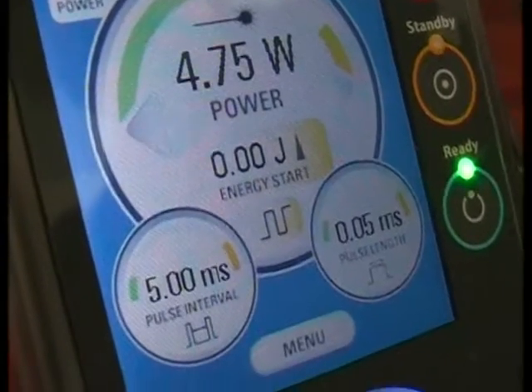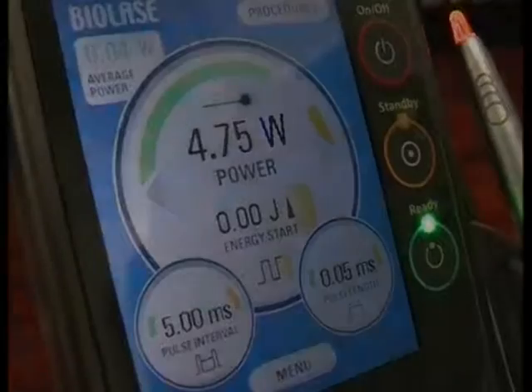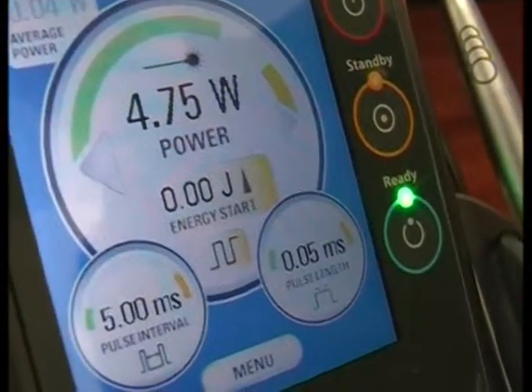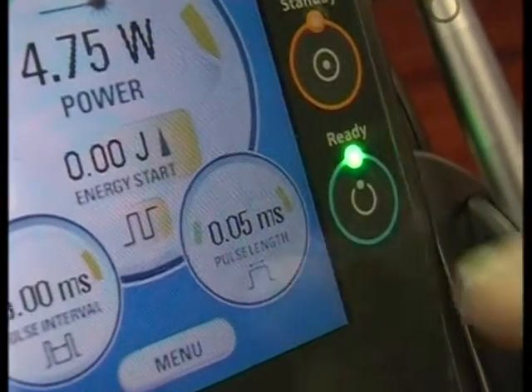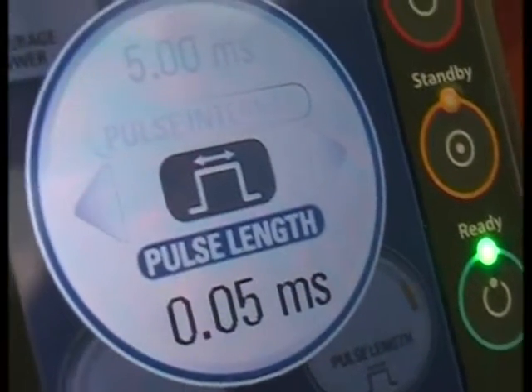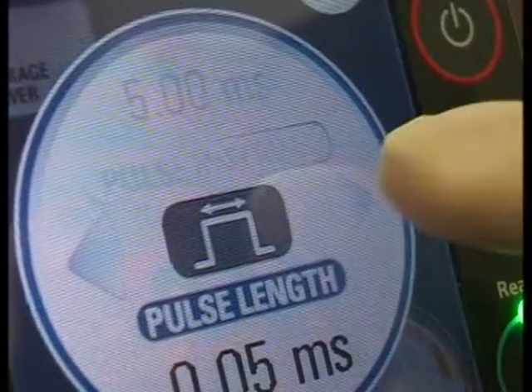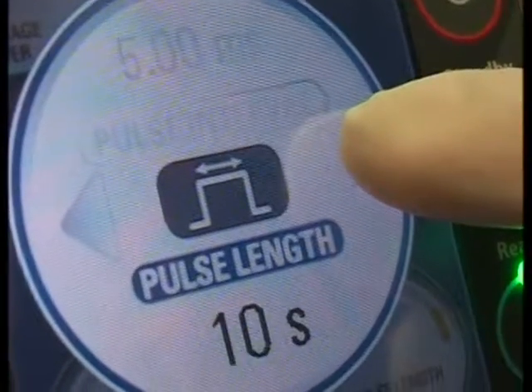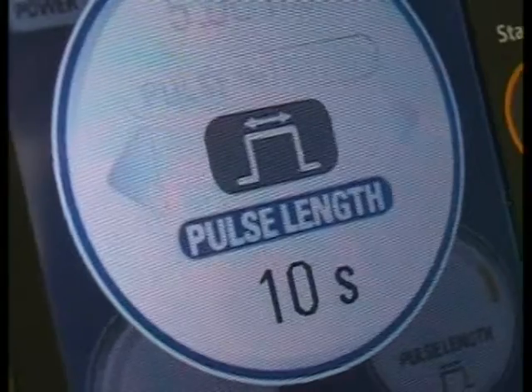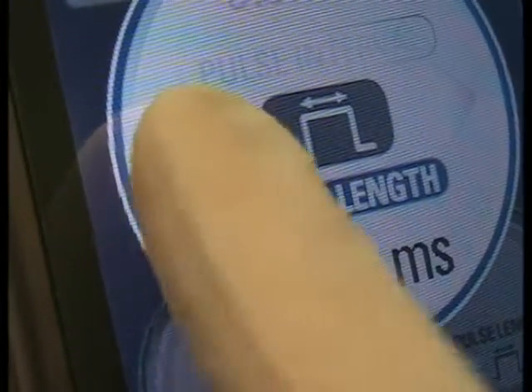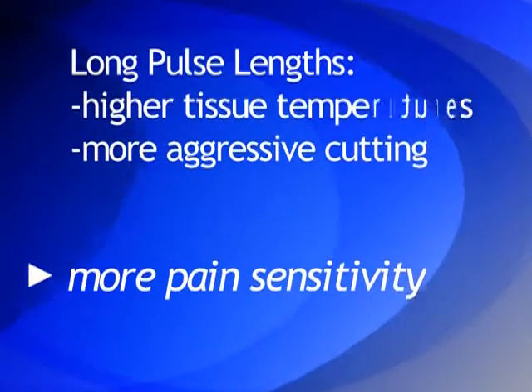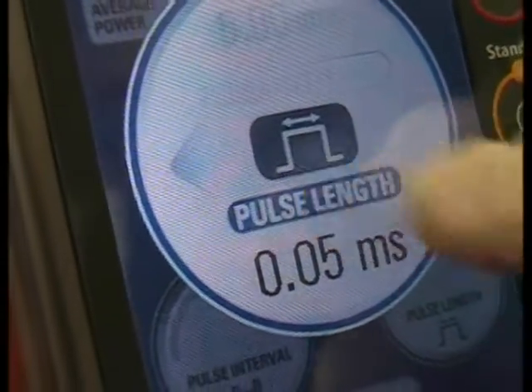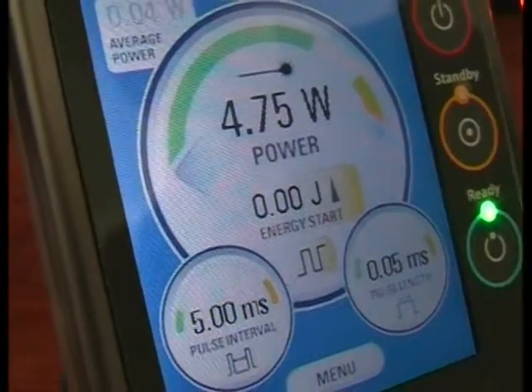You may wish to vary the pain versus cutting speed trade-off using this pulse interval control depending on the patient and the procedure undertaken. On the other side of the screen is displayed the pulse length. This is the length of time that each burst of energy lasts. This can be varied from as short as 0.05 of a millisecond to continually on. The longer the pulse lasts, the more energy is delivered without a break, and the higher the tissue temperature rises. Longer pulse lengths are thus associated with more aggressive cutting and more pain sensitivity. You can lengthen and shorten the pulse length as shown using these buttons on the touchscreen, or again in a similar way using the click wheel.